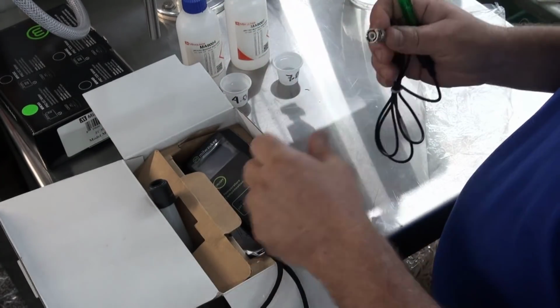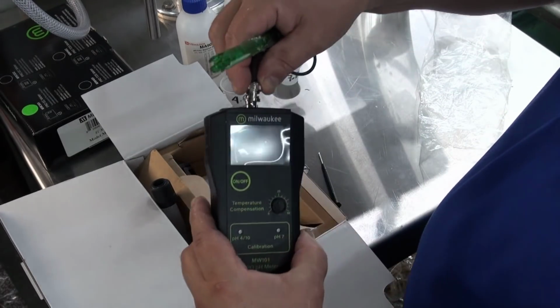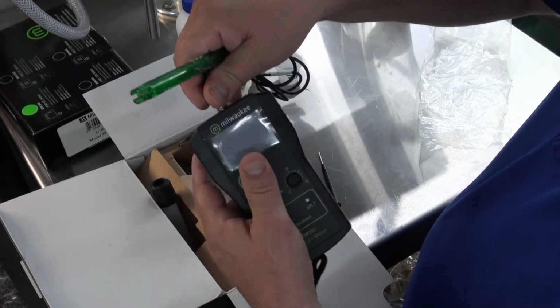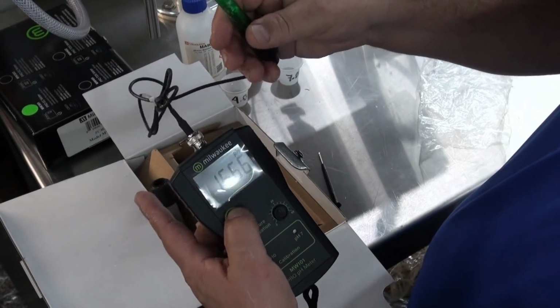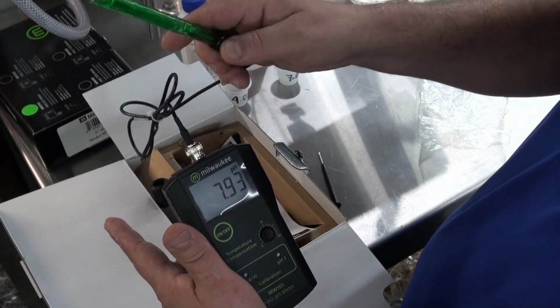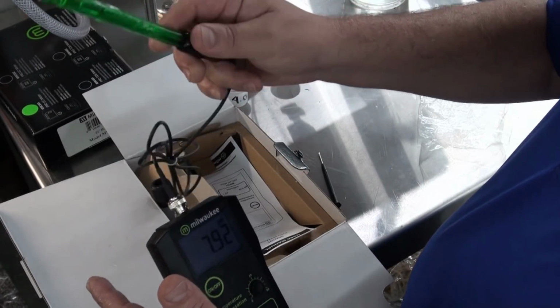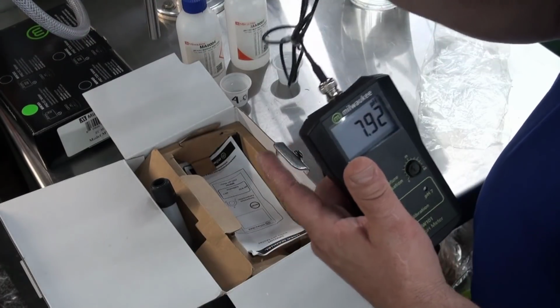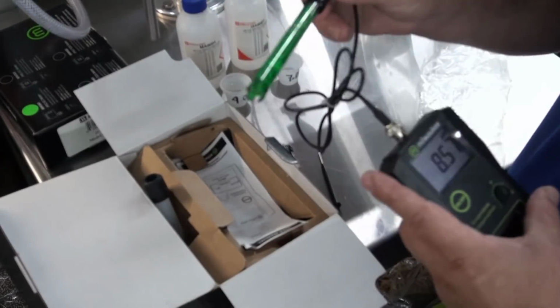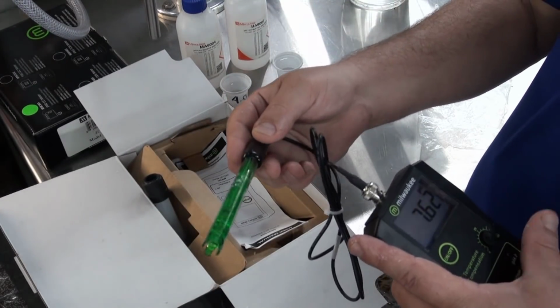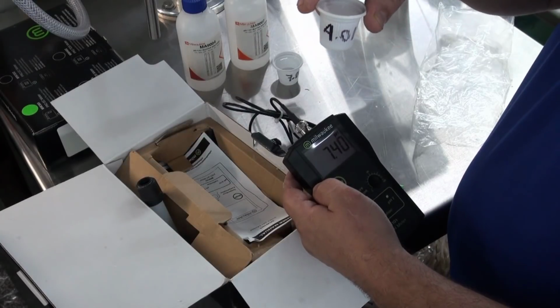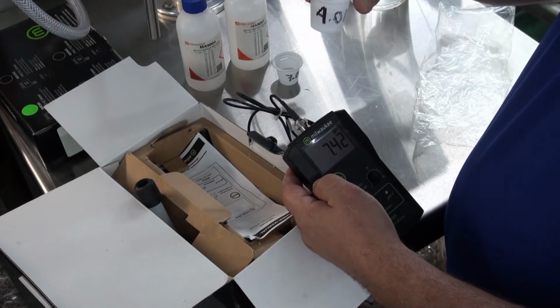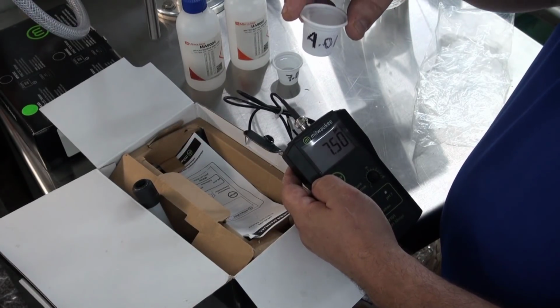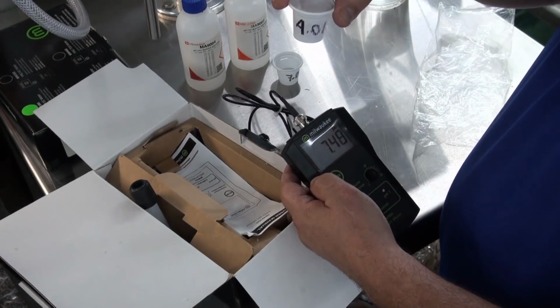This gets plugged directly into the probe itself. The probe gets plugged directly into the unit through a BNC connector. Now what I'd like to do is, normally I clean them, so I'm going to stick this in a tank. You're not going to see it, but I'll stick this in a tank, clean it off, rinse off that storage solution rather. Okay, I already filled up the solutions for calibration, 4.01 liquid and 7.01.